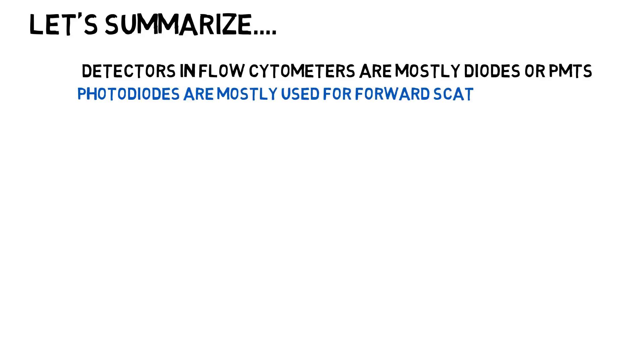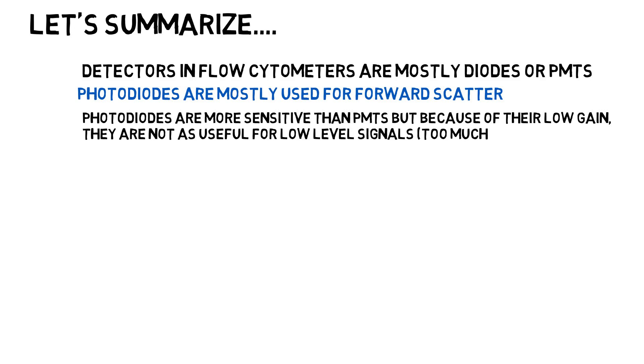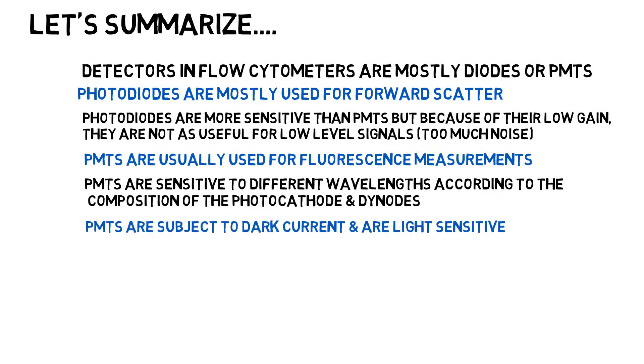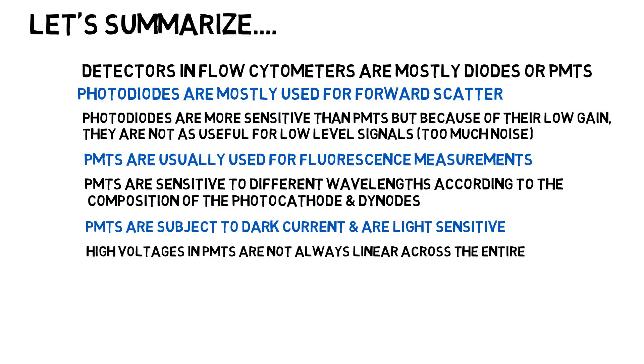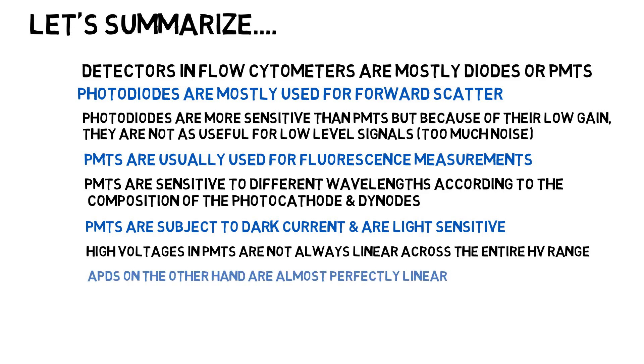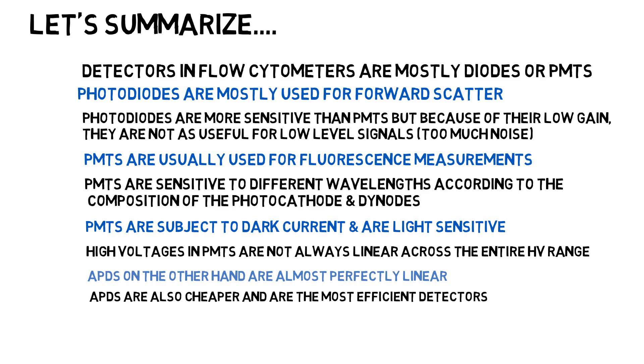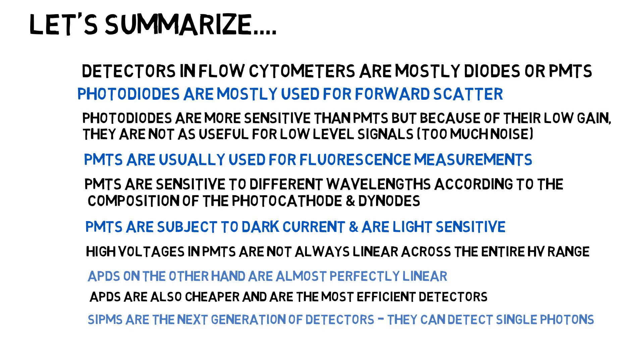To summarize: detectors in flow cytometers are mostly diodes or PMTs. Photodiodes are mostly used for forward scatter but, because of their low gain, are not as useful for low-level signals due to noise. PMTs are usually used for fluorescence measurements and are sensitive to different wavelengths according to the composition of the photocathode and dinodes. PMTs are subject to dark current and are not always linear across the entire range. APDs, on the other hand, are almost perfectly linear, cheaper, and the most efficient detectors. SiPMs are the next generation and can detect single photons.